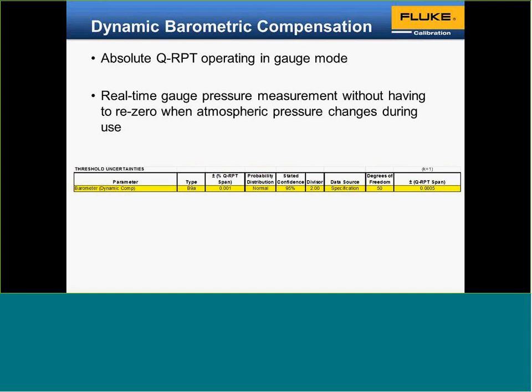Many of the PPC products, PPC3, PPC4, RPM4, when you're in gauge mode, have some way of dynamically compensating the gauge pressure with an onboard barometer. The PM has that feature: real-time gauge pressure measurement without having to re-zero when atmospheric pressure changes during use. A barometer is continually monitoring barometric pressure and adjusting your output.